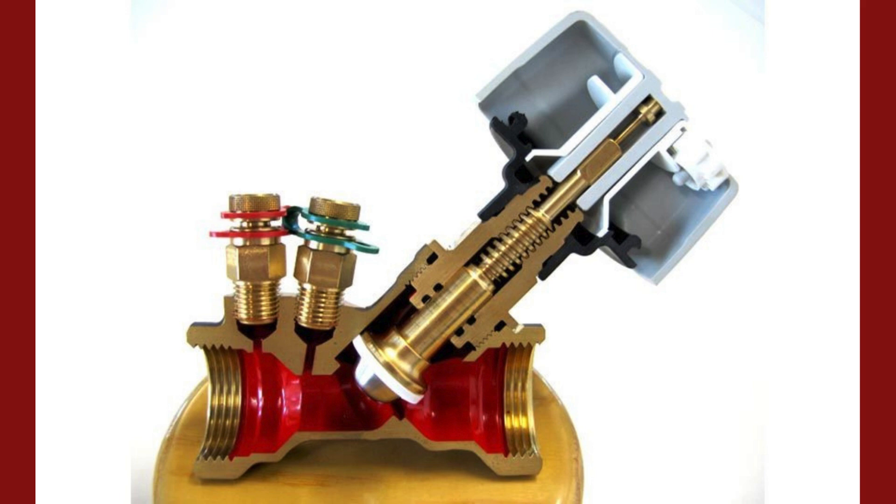2. Adjusting valves: manually operated valves are adjusted to achieve the designed flow rate through each cooling coil in the system. This might involve measuring pressure differentials across specific points.